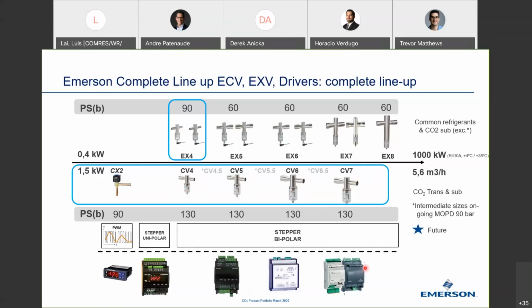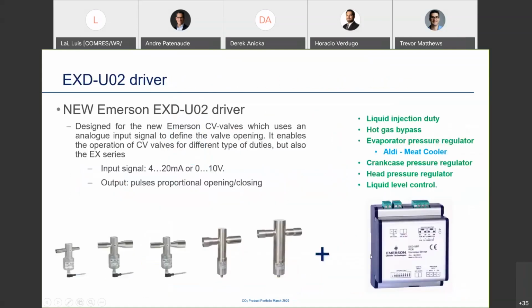Now, controllers, Emerson Dixell CO2 high pressure control. For that application, you've got superheat controls. If you're going to use these valves on unit coolers, we have superheat controls that work extremely well. And if you're going to use the valve as a hot gas bypass valve, as an EPR valve, as a suction pressure regulator valve, then you need a universal driver. It's kind of a dummy control that takes an analog in and drives a valve based on that analog signal. And this is really what we're talking about.